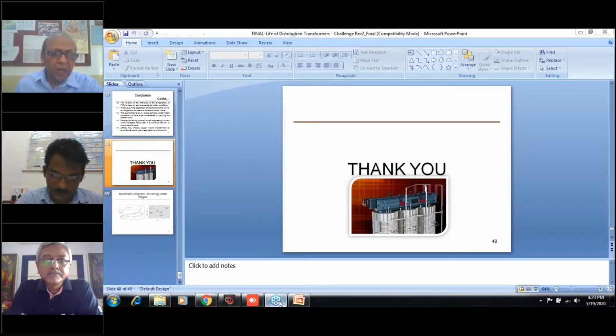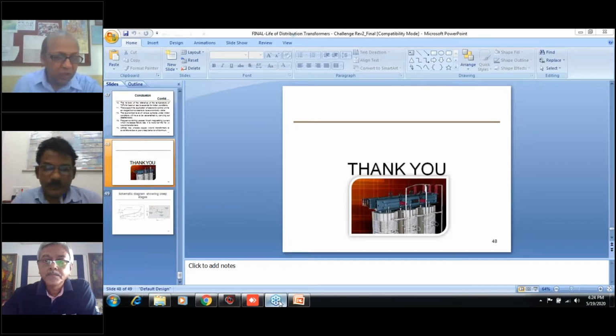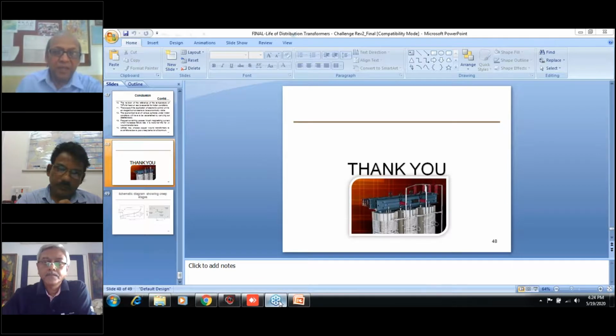See, I am not in favor. You can put a circuit breaker inside or outside - protection you can do, but if the inherent strength of the transformer is not good, then it is not going to help. You provided these self-protected transformers, you did not succeed. You provided circuit breakers, you could not succeed. They are good when the inherent strength of the equipment is good. If the inherent strength of the equipment is not good, its reliability is poor, then it is not of much help, because whatever the circuit breaker will operate, before that, stress has already appeared in the transformer and some damage has already been done. You have saved the damage of time, but some damage has already been done. It is more in case when creep is more or fatigue is more.